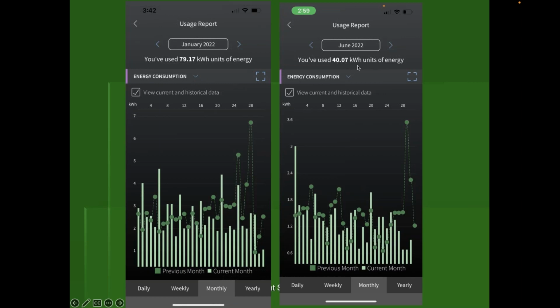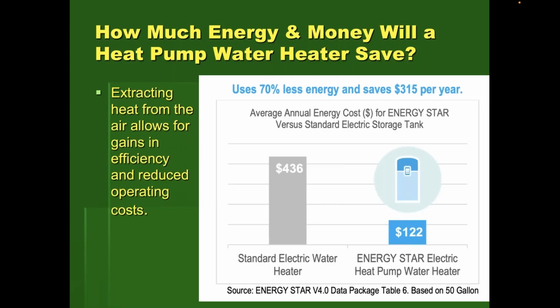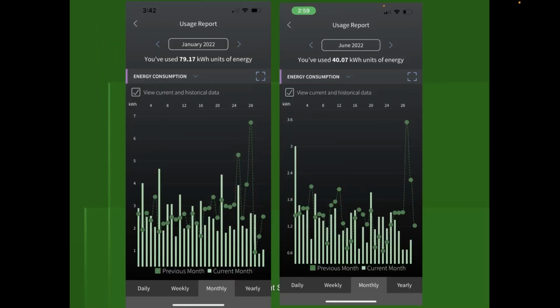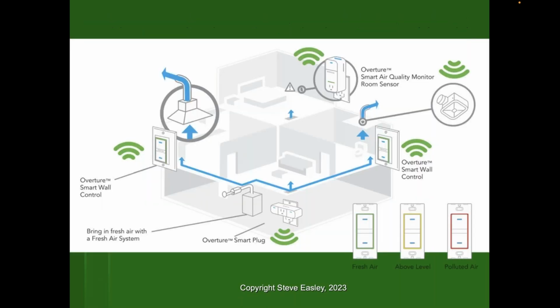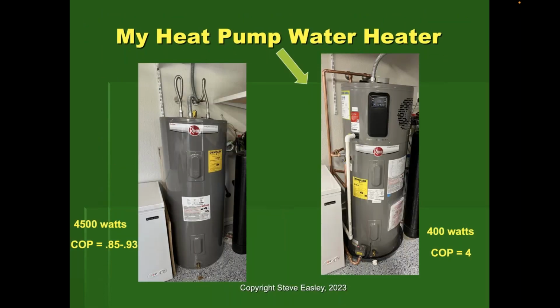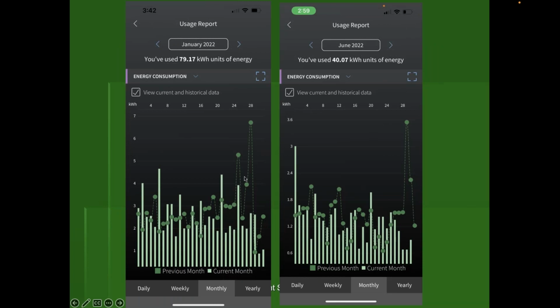Now look at this in June. I used 40 kilowatt hours. Anybody want to take a guess why? With an average of less than 1.5 a day? Because I'm in my garage, and the garage gets upwards of 95 degrees. So let me go back here and show you this. Hang on a second, I'll find it. Sorry, there we go. So this being in my garage, my garage is like 95 degrees, so the COP of my water heater went way up because it's so hot. In the winter months, it's probably closer to the 40 degrees range. So the bottom line is that no matter what time of year it is, you're still saving energy over traditional systems. But I just thought you'd find this fascinating, to see how much less energy you use with one in the garage in the summer versus the winter.